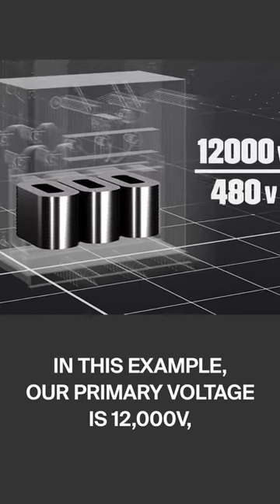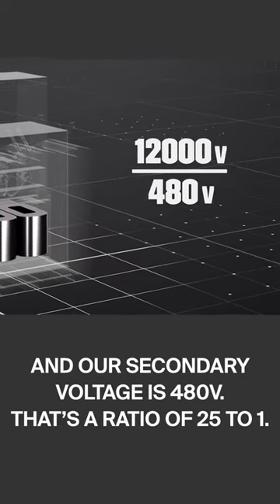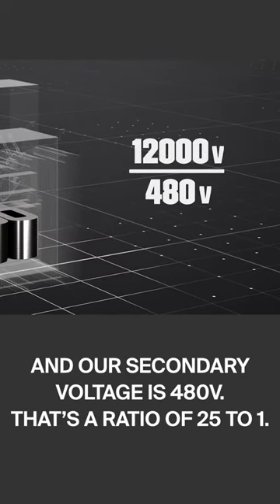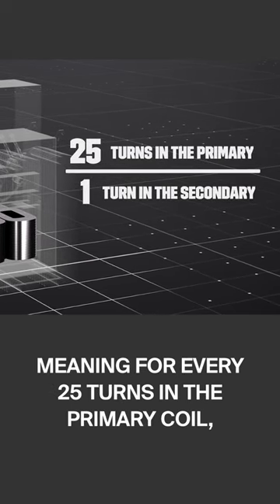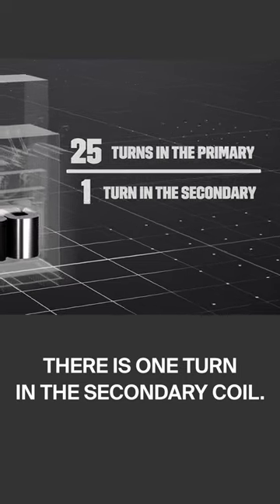In this example, our primary voltage is 12,000 volts and our secondary voltage is 480 volts. That's a ratio of 25 to 1, meaning for every 25 turns in the primary coil there's one turn in the secondary coil.